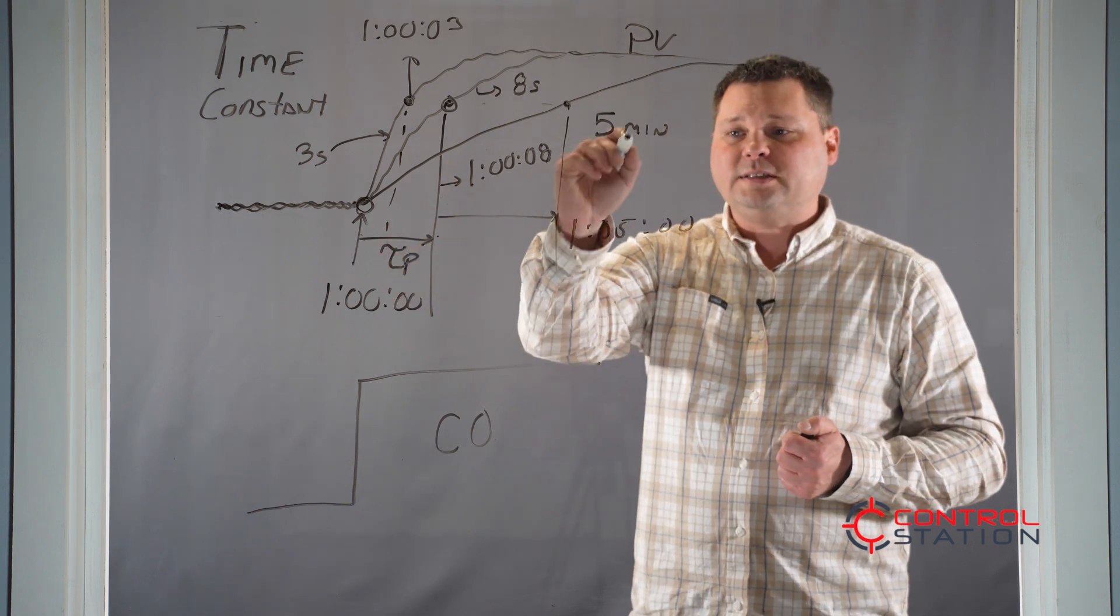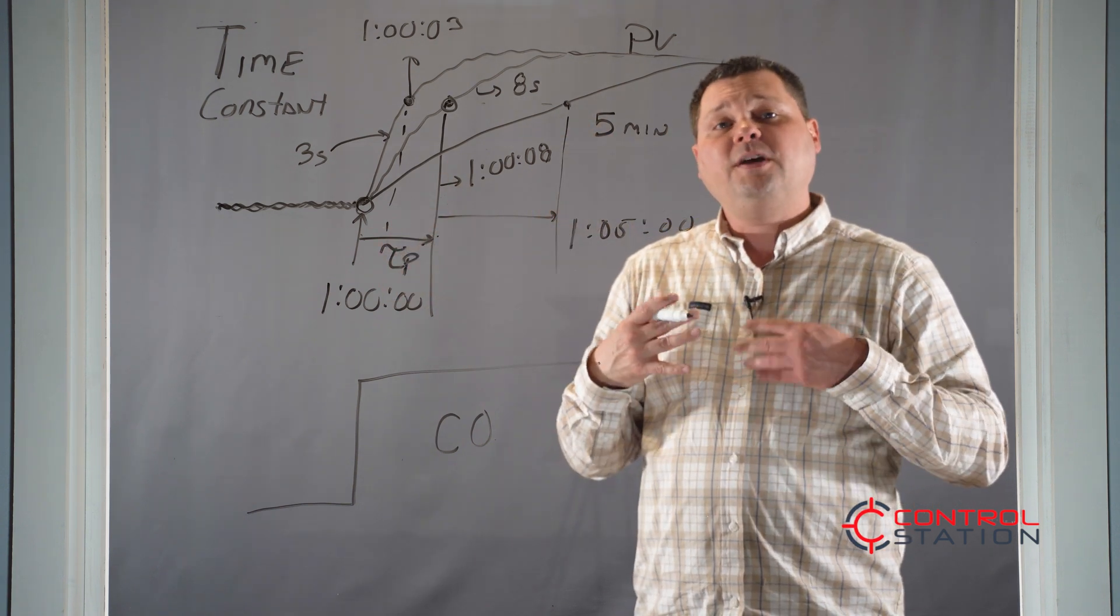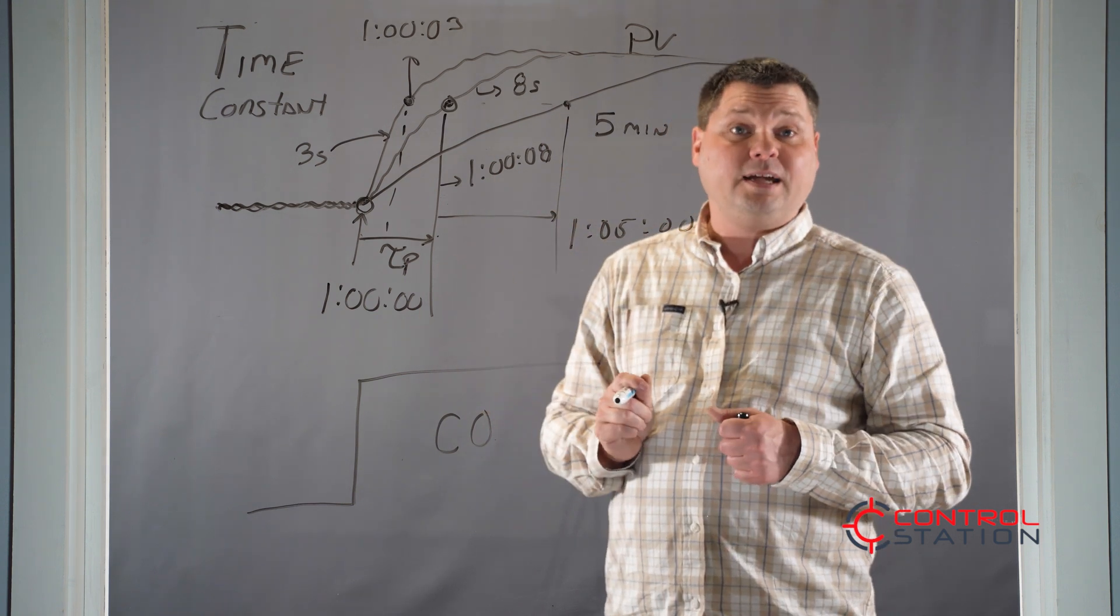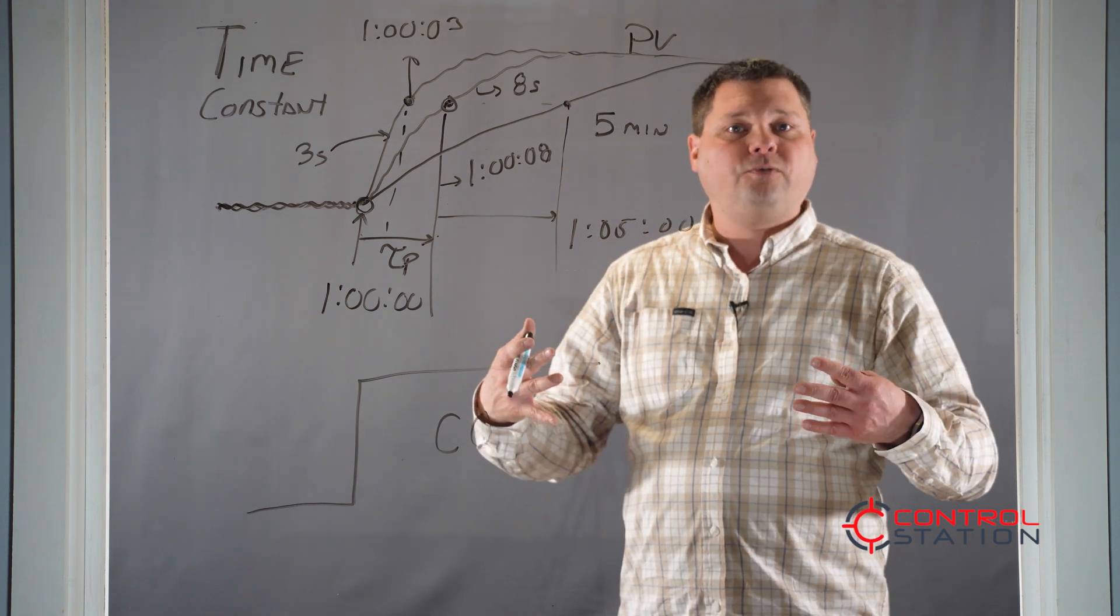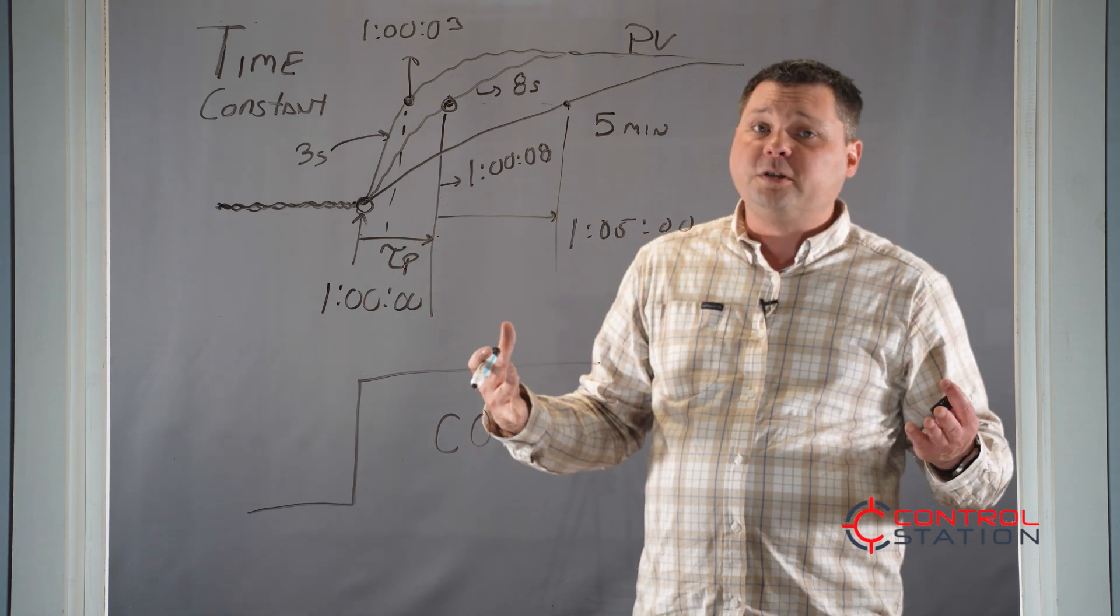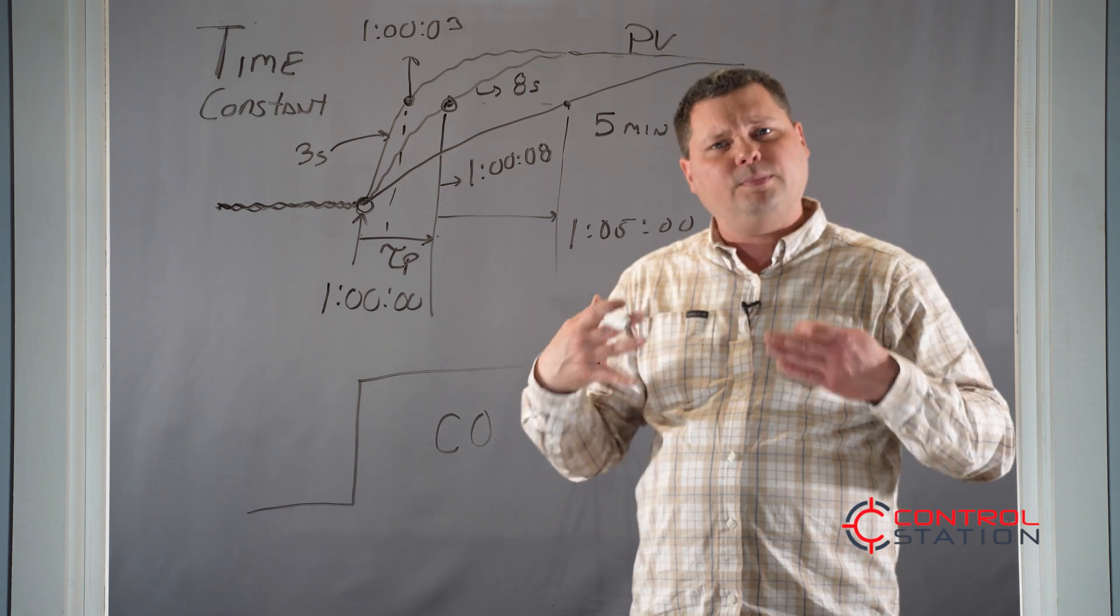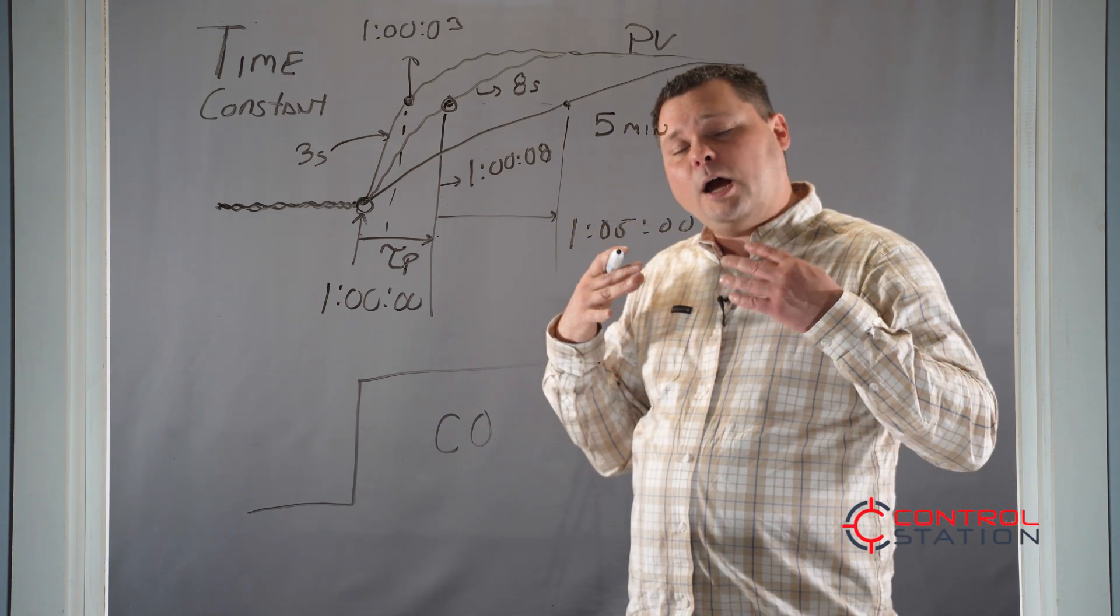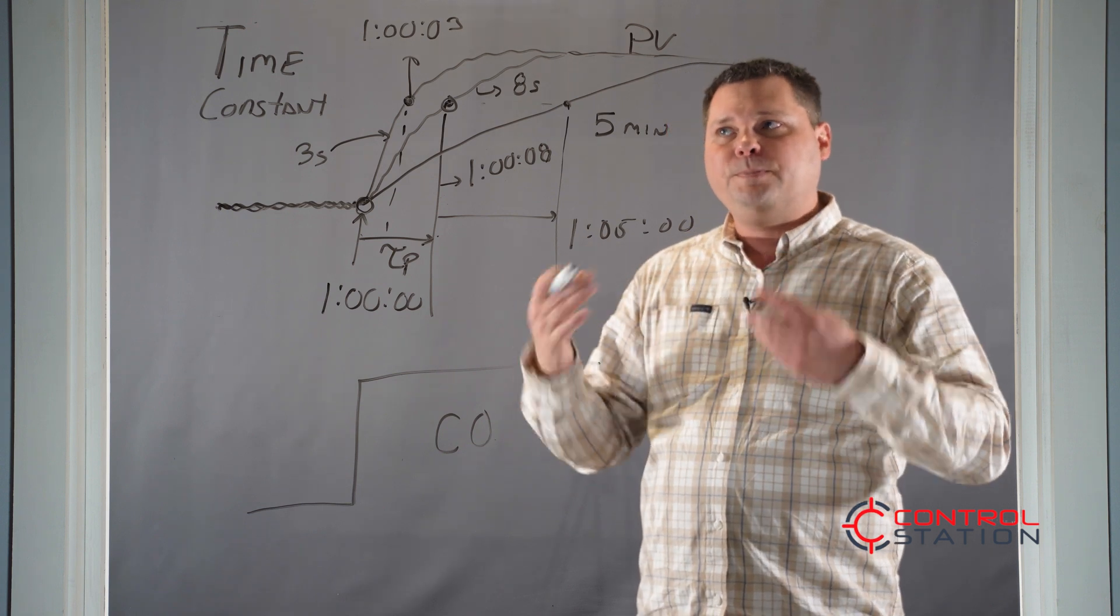If we've got a five-minute process time constant, it would be difficult to expect this loop to be able to get to a set point in five seconds. It's unnatural for the process to move significantly faster than this process time constant. You can force it in some ways, but you'd reduce the stability and robustness. So use this to help yourself understand the speed of the system.